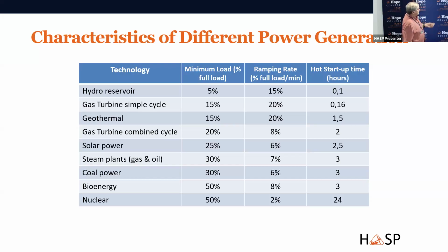A gas turbine, simple cycle, that doesn't have that heat recovery piece, its minimum load is about 15%. Again, that shaft and that mass of metal you have to keep rotating, what's the minimum level you can run? You can't run it real slow or it doesn't work. So there's a minimum level of 15%.